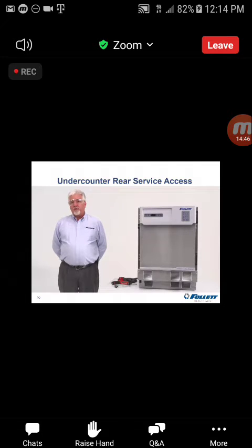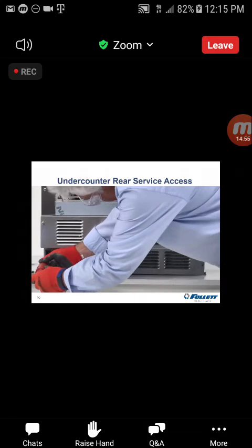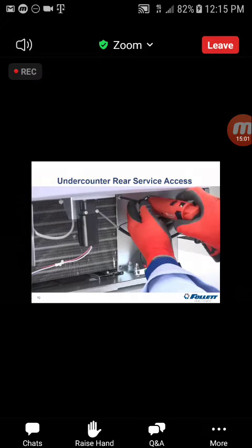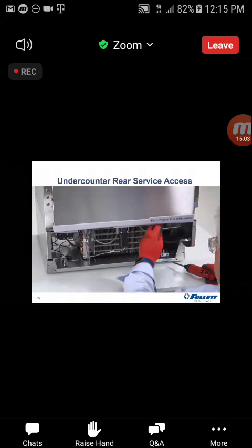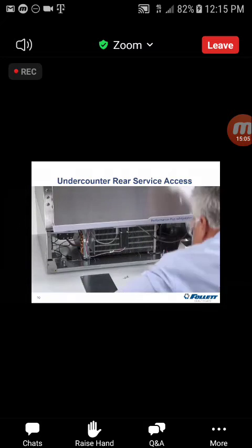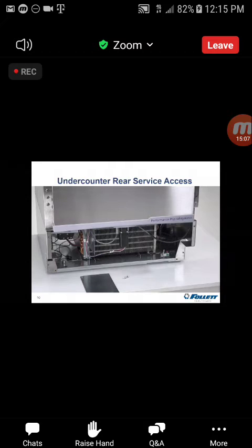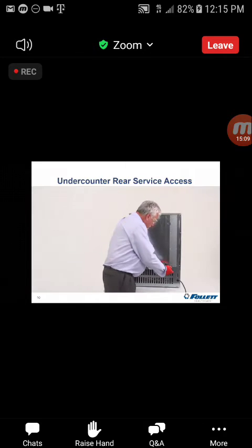To access the condensing unit on Follett under-counter refrigerators and freezers, the unit can be partially withdrawn from the rear of the unit without having to disconnect any refrigeration components. The first step would be to remove the front cover, the bottom of the unit, and to remove the baffle from the right-hand side of the condenser. It is very important at the end of the service that this baffle be reinstalled to ensure proper airflow during normal operation.